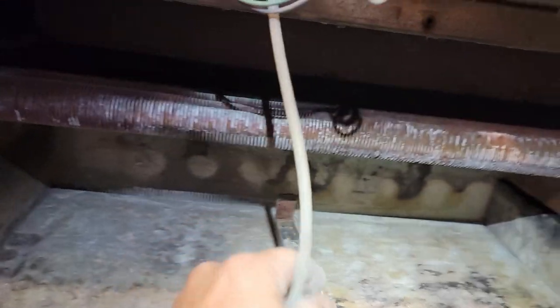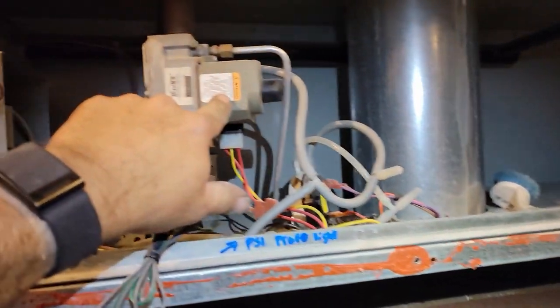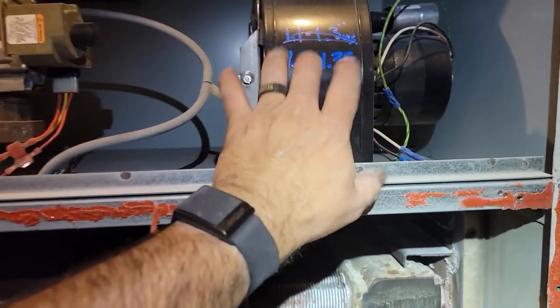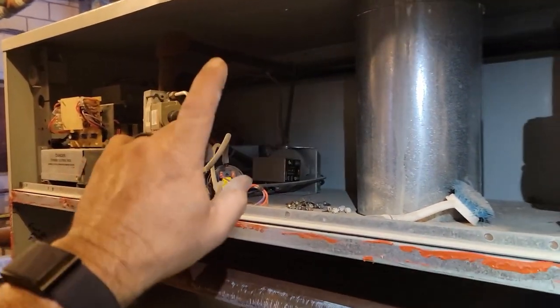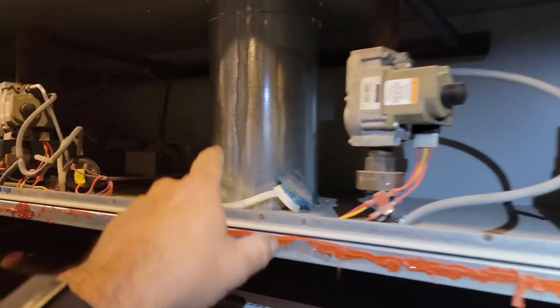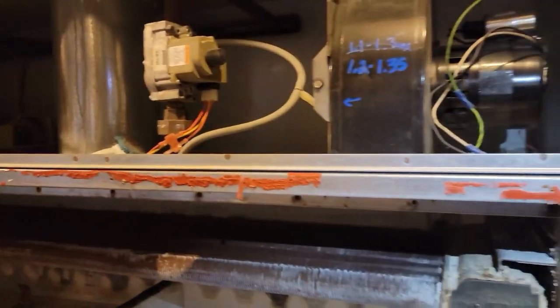You got a differential, you got to set your differential point there and you got to tap onto the one that comes down here to the burner chamber, because this burner chamber is pressurized. First thing I did was set this up for the 1.2 to 1.35. Once that was set, then I set this gas valve. You got to put the cap back in the gas valve to get an accurate reading. It's very sensitive to that. Factory said this is an 04.